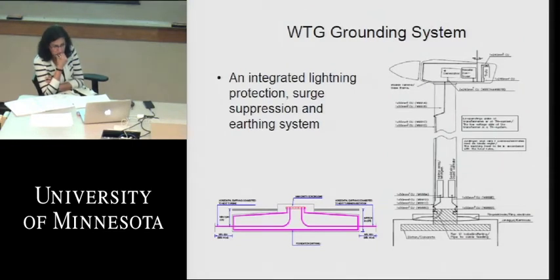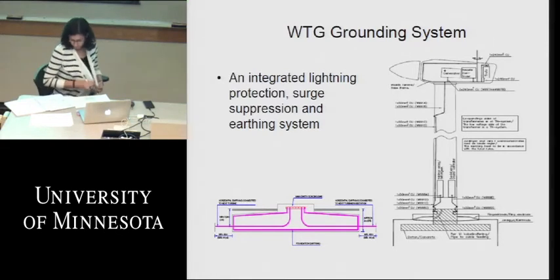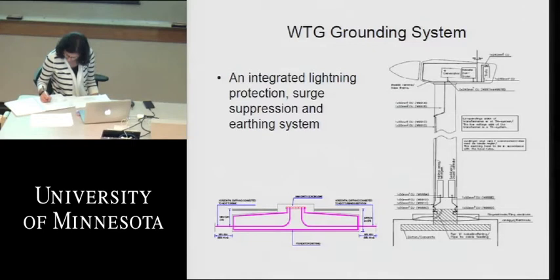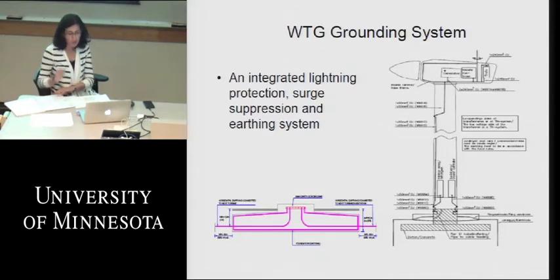The grounding systems within a wind turbine are extremely important, because lightning is one of the major damage methods that really can bring down a turbine. So it's got this integrated lightning protection, surge protection, and grounding system all built in to the standards for lightning and for grounding. So we actually put lightning receptors into the blades to attract the lightning to these receptors, so that they don't hit odd places on the blade and crack our fiberglass shell on the blades, which would cause turbulence on the blade itself and reduce power output. So those receptors in the blades have got conductors that bring any energy from a lightning strike through the blade roots and the blade bearings that allow the blade to rotate, bring it through the hub itself, and then bring it into this integrated system we have with the wind turbine.